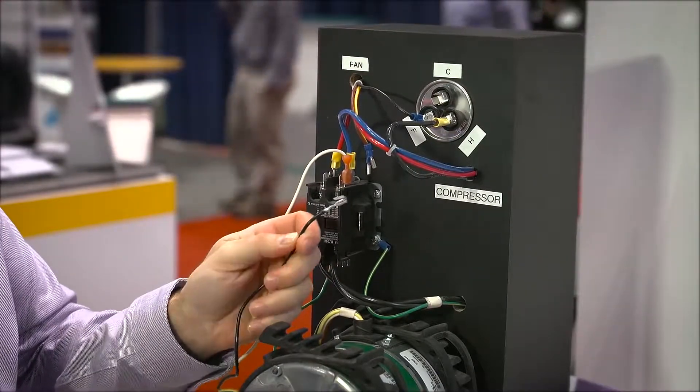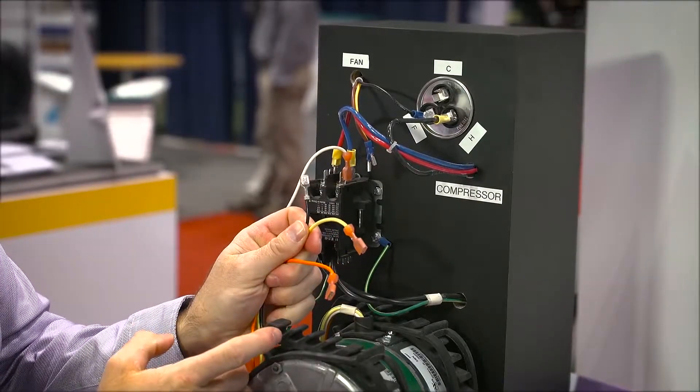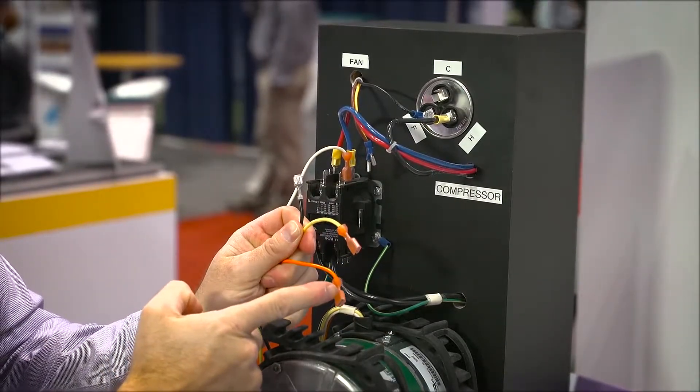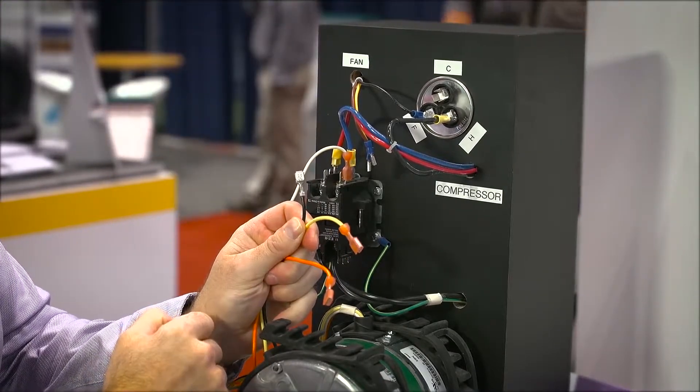But before we connect the black wire we want to find the orange and yellow wires to determine whether we're replacing an 8-pole, 825 rpm rated motor or a 6-pole, 1075 rpm rated motor.